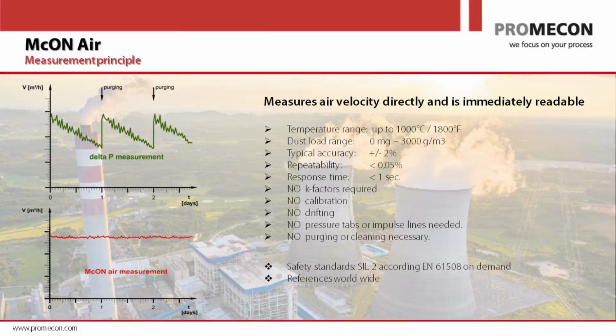We don't care how big the signal is. And that has a huge consequence. If the sensor gets dirty, if the sensor has some issue, if there's some problem, you will never see a different value. You will always see the same value because the time shift does not change. The time shift is always constant. So the consequence is that the system is installed in your plant, and then you forget about it. And it's the same for primary air, for secondary air, for OFA. You will never have to climb up to the sensors and do traverse measurement and double check. That's negligible. You don't need that.